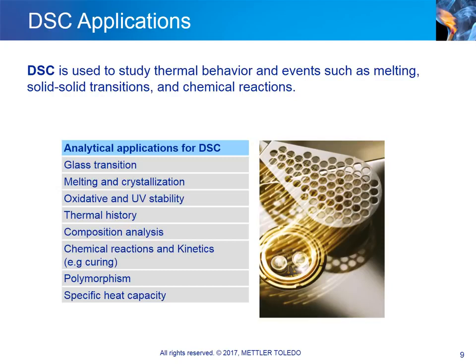Mettler Toledo has also developed versatile optical techniques that allow you to observe changes that occur in a sample while it is heated or cooled. The techniques include DSC microscopy and DSC chemiluminescence. The photocalorimetry option is used in combination with the DSC and allows the study of the curing process for adhesives or paints under visible or UV light.